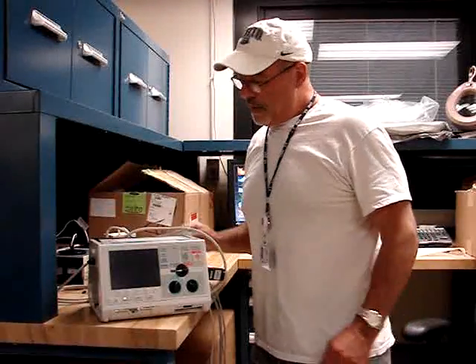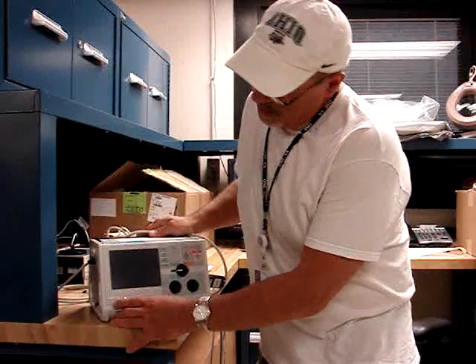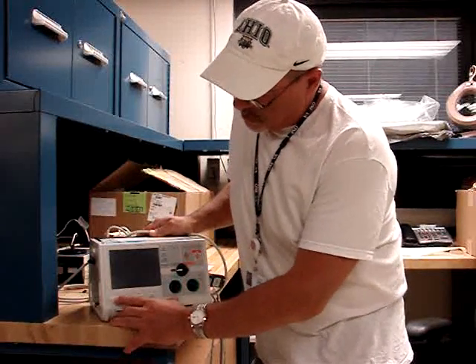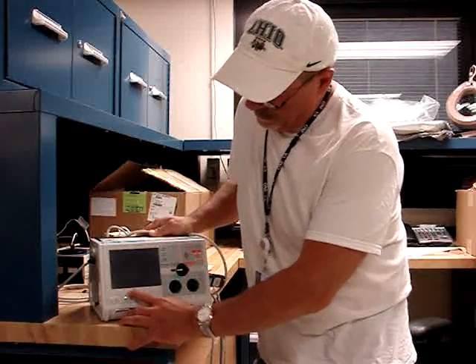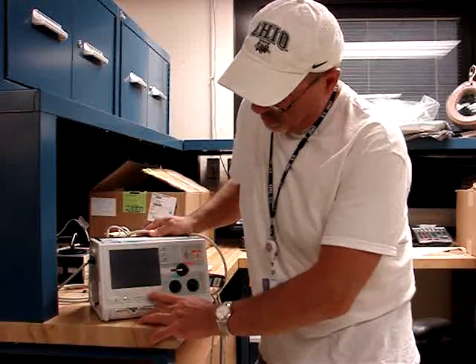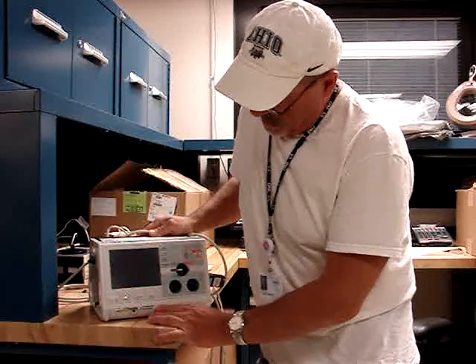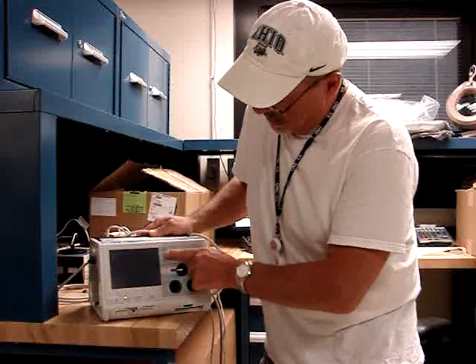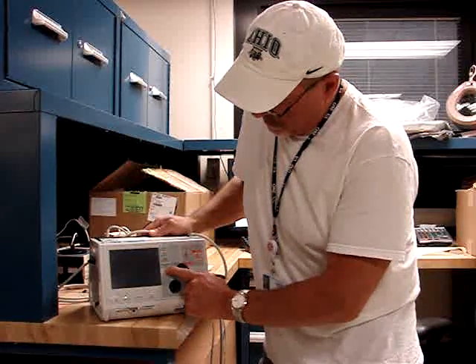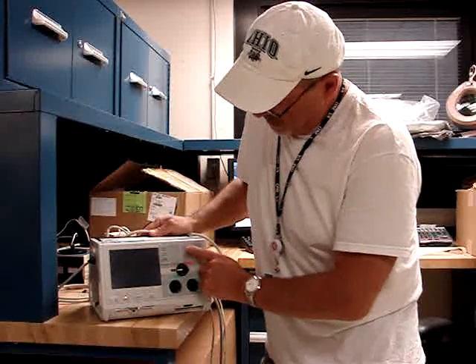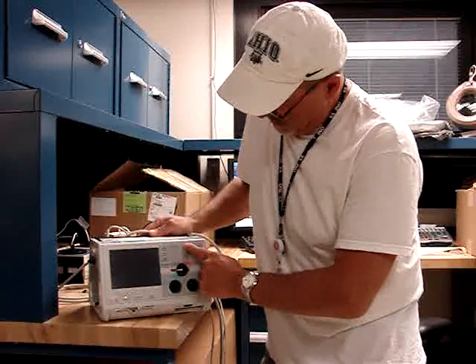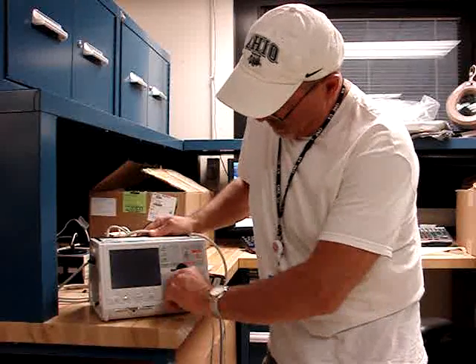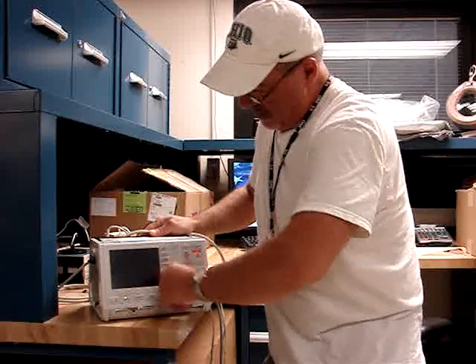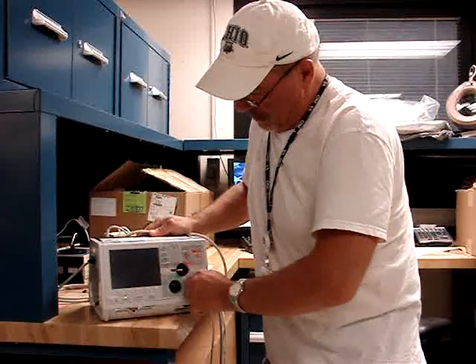Okay, this section of the preventive maintenance, I'm going to check the positive reflex of the buttons, make sure they rebound properly all the way across. Check all of them: summary, mode marker, lead, size, alarm suspend, recorder, charge, analyze, and then check all the actual buttons. Go full travel on them.